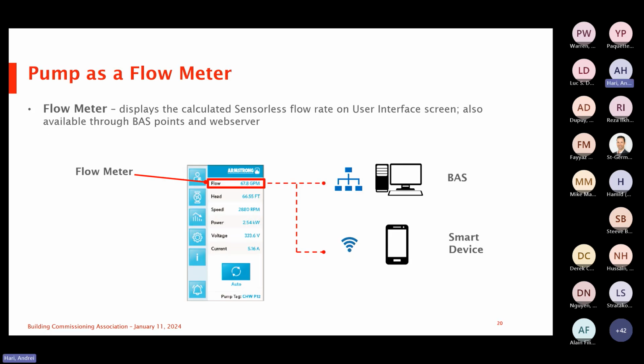The other thing now is the data output. This is the Armstrong version, but the Danfoss VLT drive has the same parameters. You'll have flow as an output, you will have head, speed, power, voltage, and current. All of those data points are being read from the drive, and they're visual. So the beauty about commissioning is that when you are setting up the pump, instead of trying to look at a pump curve and validate flow, you actually have the validated flow value right at the drive. I've been in projects that are very complex, where you have primary and secondary, and you can just see what the flow is doing.